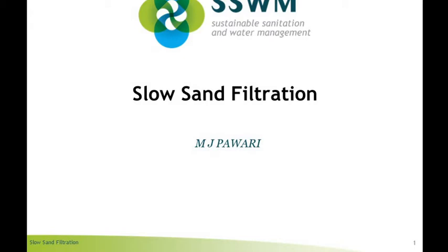Okay, so yesterday we discussed the slow sand filter and the different actions involved in the filtration process. The first is mechanical straining, where the suspended particles cannot pass through the bed of sand. Next is sedimentation, where the voids between the sand particles act as small sedimentation tanks, and the colloidal matter obstructed in the sand bed settles out through a process of sedimentation.